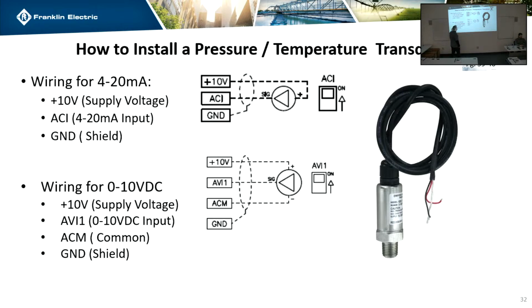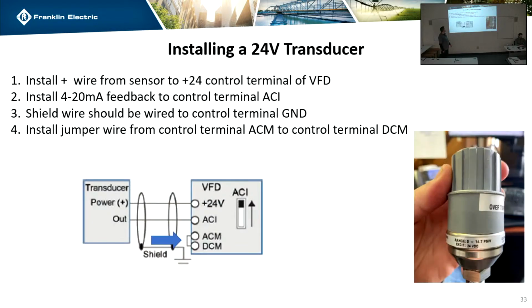And if you're using shielded cable, you just lay it on the ground right here, and that's what that's referencing as a shielded cable. Do you have to jump something on the drive though? Nope. If you have a 24-volt transducer, it's just as simple, but you're using 24 instead of the 10, and then you've got your ACI. This one, you would have to jump the ACM and DCM, and then your shield goes to ground. That's most likely what you guys would use in the field.